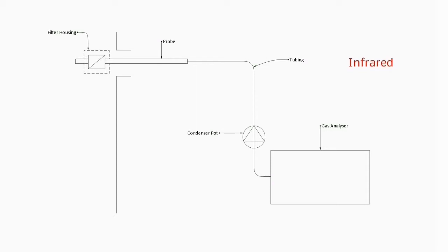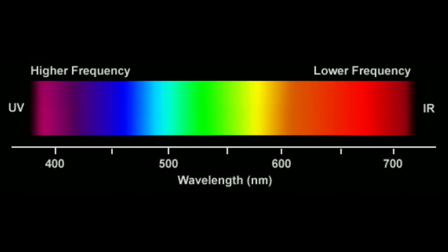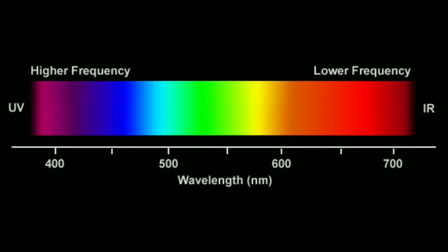Infrared and ultraviolet are some of the areas of the light spectrum that are utilized to continuously measure various gas concentrations. Different molecules in the air absorb different frequencies of light. Air with lots of a certain gas will absorb more of a certain frequency, allowing the sensor to report a high concentration of the corresponding molecule.